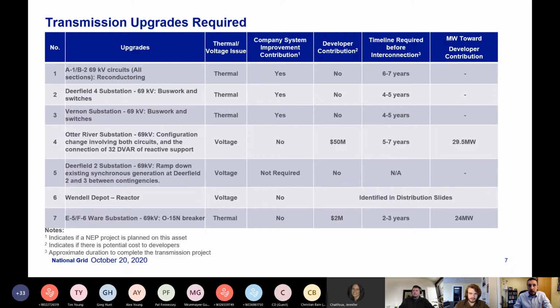That's going to essentially add a dynamic VAR compensator, which will be there for voltage support of the transmission line. That's exclusively because of the DG coming on and the effects it's having on transmission. It's estimated to be a $50 million effort with a 5 to 7 year timeline for interconnection.